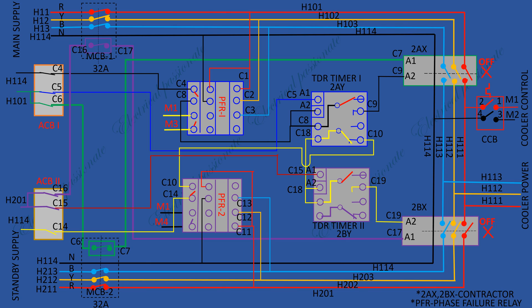Now suppose MCB1, MCB2, ACB1 and ACB2 are switched on. PFR1 gets power and makes its contacts. TDR timer 1 gets neutral connection at A2 after pre-setting time. This contact makes the circuit to power contactor 2AX by throwing neutral at A2. The 2AX contactor gets energized and connects three-phase power at H113, H112, H111. Now cooler power is on main supply.